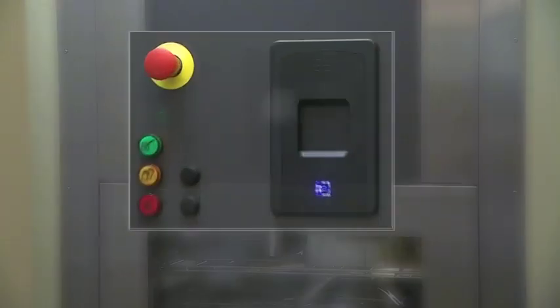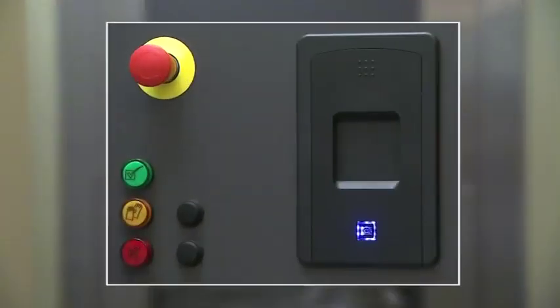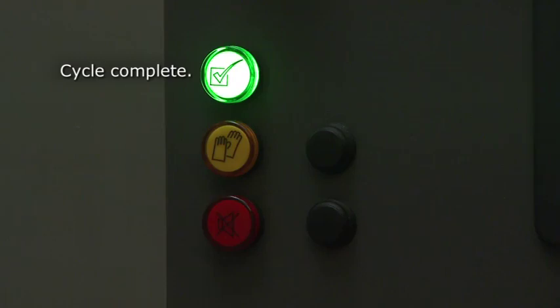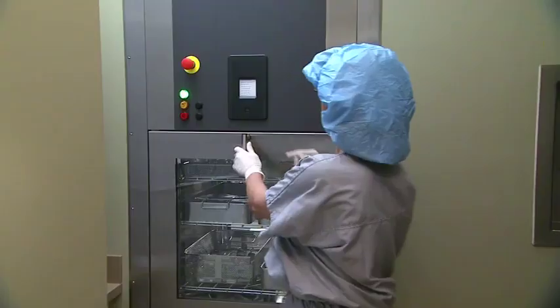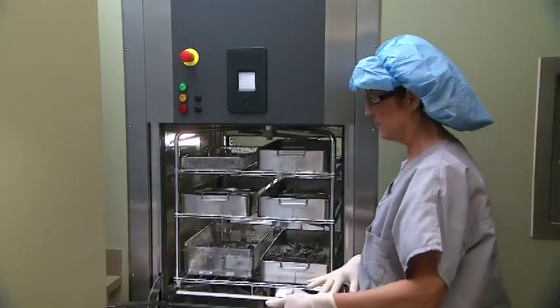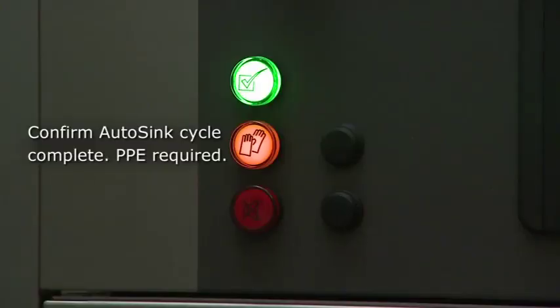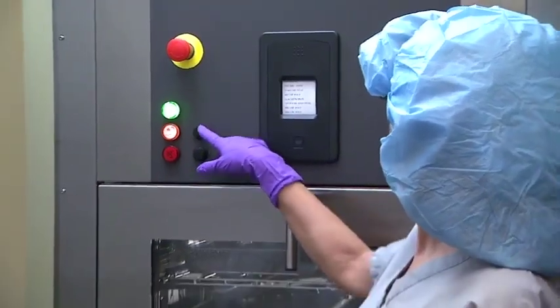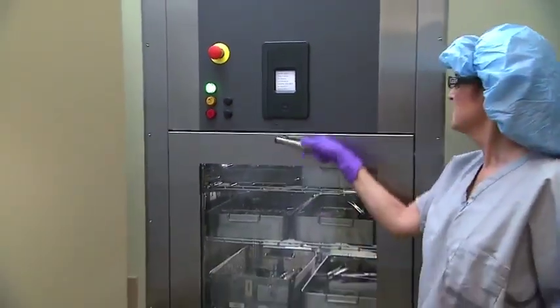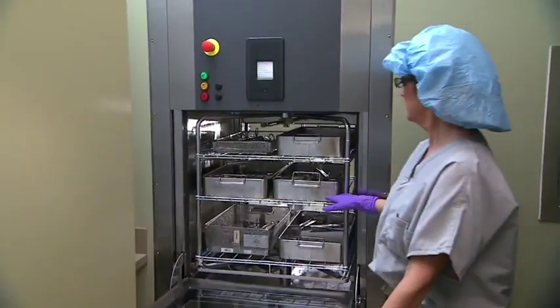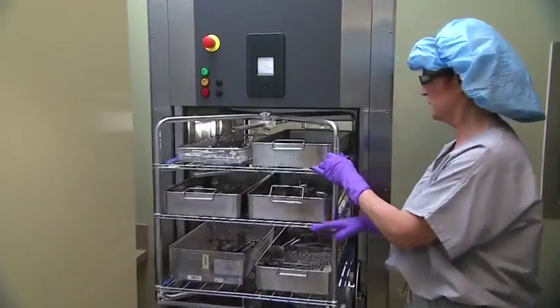Double-door units are equipped with 4 indicator lights: green, yellow, red, and blue, plus 2 confirmation push buttons on the unload side. The green light indicates the cycle was completed and the parameters for disinfection were met. The unload door can be opened to remove the load. The yellow light indicates that the AutoSink cycle has been completed and no guaranteed thermal disinfection took place. The confirmation button next to the yellow light must be pressed to acknowledge that PPE should be worn while opening the door and handling cleaned items.